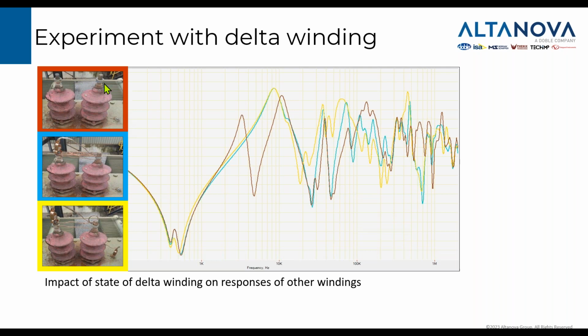I removed that connection and I simulated three conditions: one with a completely open delta, one with the delta closed but not earthed, and one with the delta closed and earthed. And here you can see responses on another winding which are completely different. So the condition of the other coils, the other windings, plays a role again.